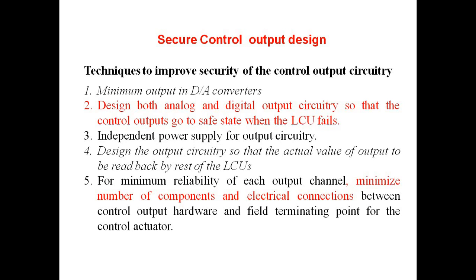For maximum reliability of each output channel, minimize the number of components and the electrical connections between the control output hardware and a field terminating point for the control actuator.